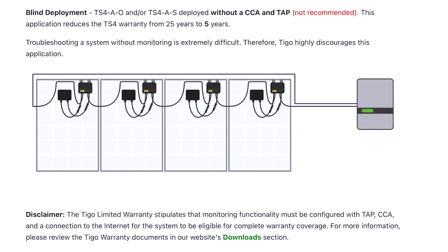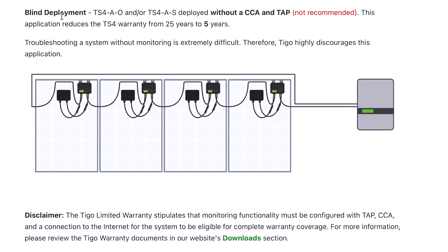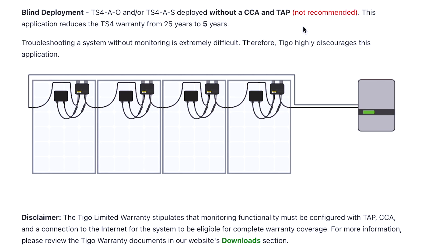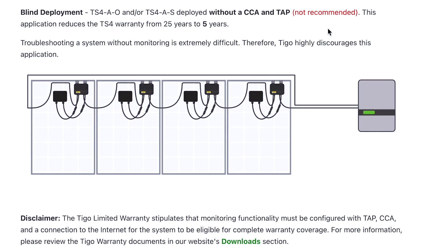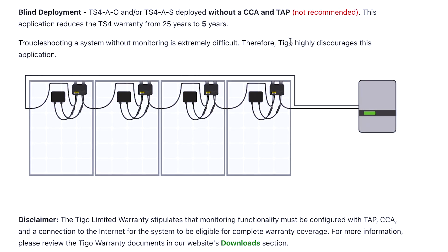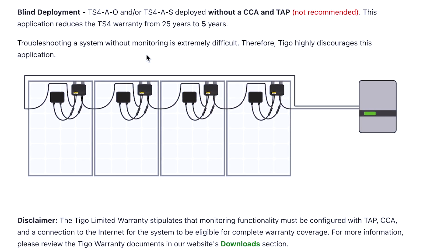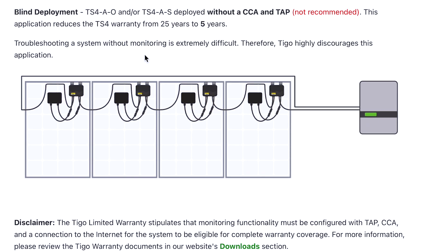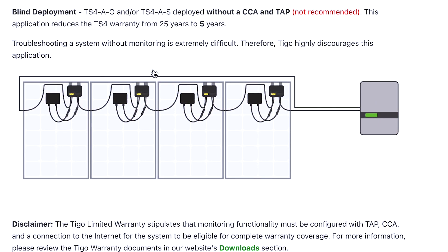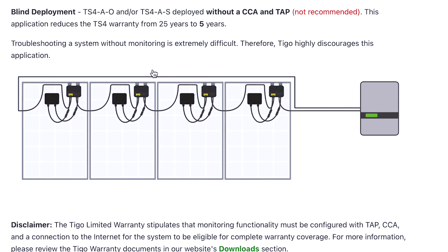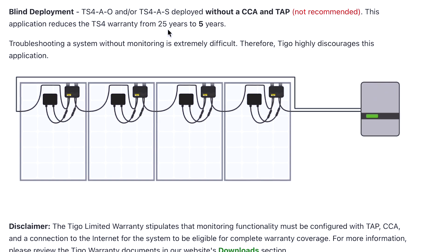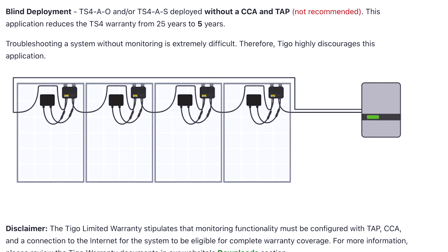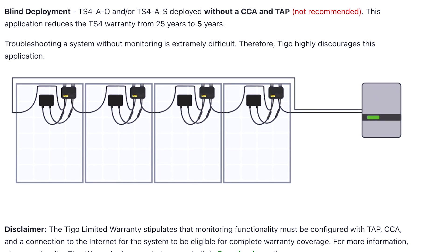Blind deployment is the one I already mentioned. Right there in red it says this is not recommended. The TS4-AO or TS4-A-S deployed without a CCA or TAP — this application reduces the TS4 warranty from 25 years to five years. So if you want to keep that 25-year warranty, go ahead and get the CCA and TAP.